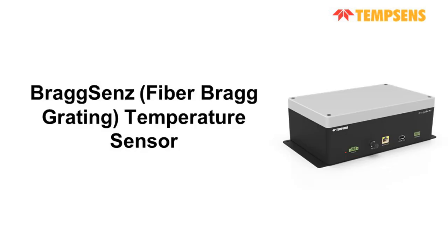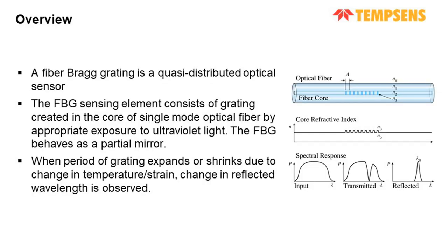So moving on to our second solution, that is BraggSenz, which is based on fiber Bragg grating technique. Fiber Bragg grating is a new and non-conventional sensing technology used in a wide variety of applications nowadays. It is designed for sensing applications where there is electromagnetic and RF interference. It is light in weight, compact, and intrinsically safe to use in hazardous environments. So this is a basic overview of the fiber Bragg grating sensors. Unlike fully distributed sensing systems, which measure temperature or strain continuously along the entire fiber length, FBGs are quasi-distributed. This means we place multiple FBGs at specific points along the fiber, each with a unique Bragg wavelength. Then by sending light through the fiber and analyzing the reflected wavelength, we can monitor temperature or strain at each FBG location independently. So basically, we put different FBGs on a single fiber at predefined locations.